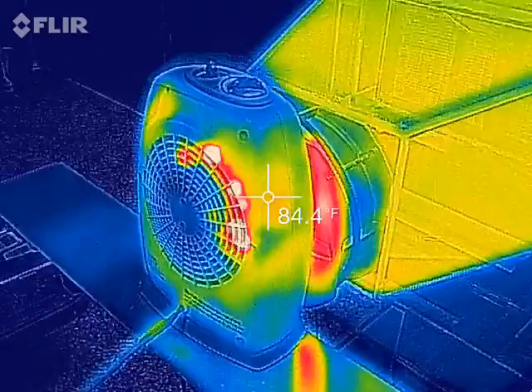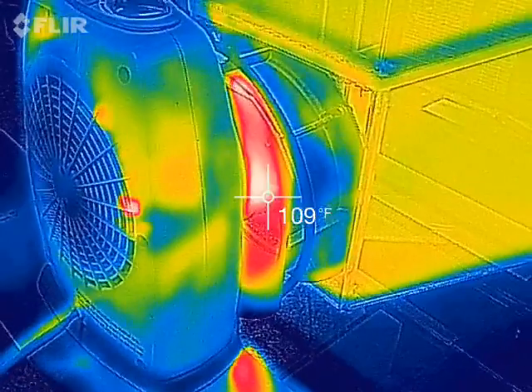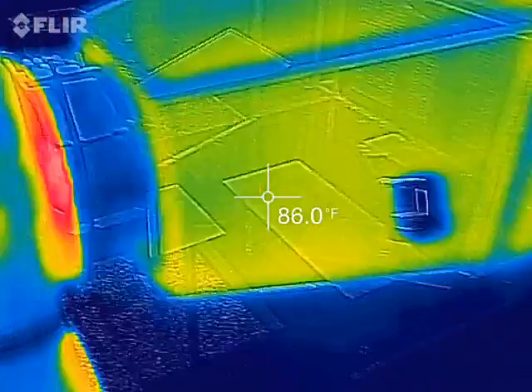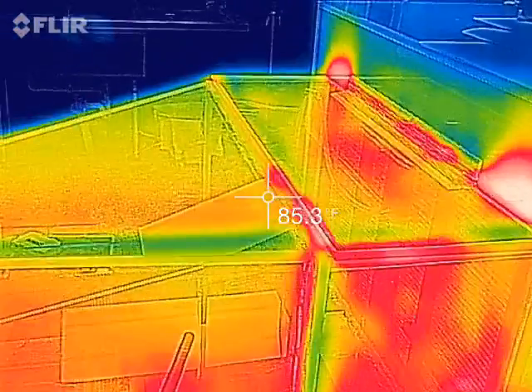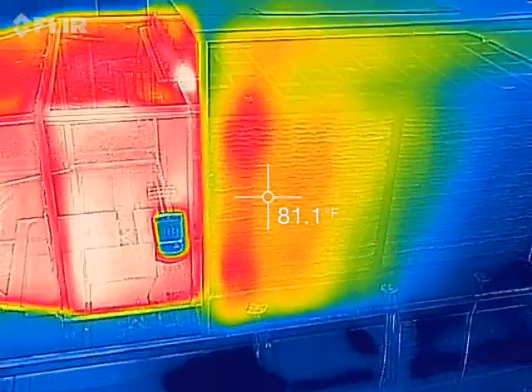Here at Oakland University in Michigan, we have a space heater producing in excess of 100 degrees Fahrenheit, almost 120 degrees into the inlet fan. We have around 102 degrees Fahrenheit inlet to the HMX, and that drops down the relative humidity to about 17%.